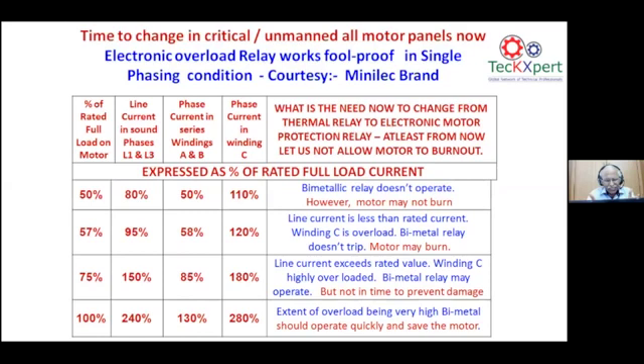So this is the next area: the problems identified in the existing systems. What is seen in the motors in many of the industries? Throughout the industries, let us say 99 of 100 industries, we are still using thermal overload relays, which are not able to sense motor loading or motor overloading in case of single phasing, current imbalance or voltage imbalance. Let us say the motor is rated at full load condition, at 50%, 57%, 75% and 100% load. In case single phasing happens, with the sound phases being L1 and L3 and the weak phase L2, you find the bimetallic relay, on the right side, which we have been using throughout the decades in our motor systems.